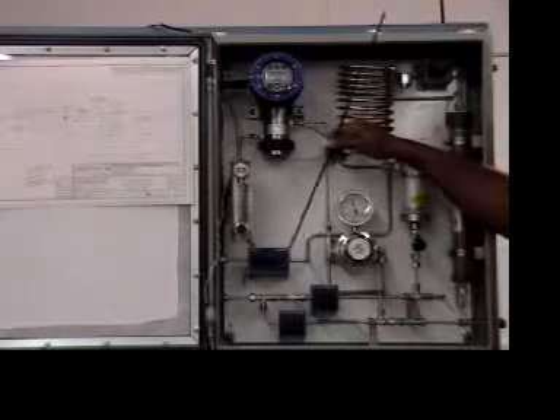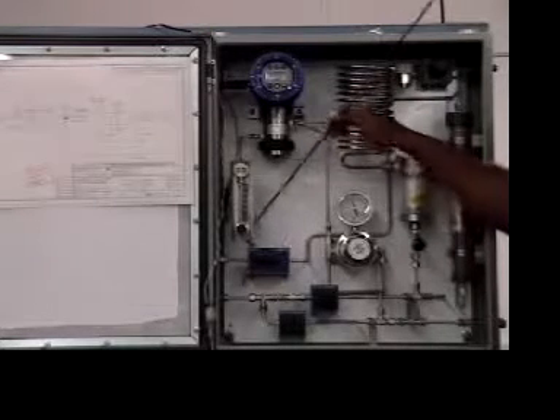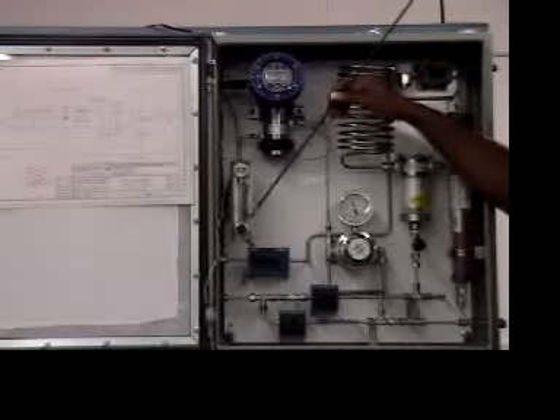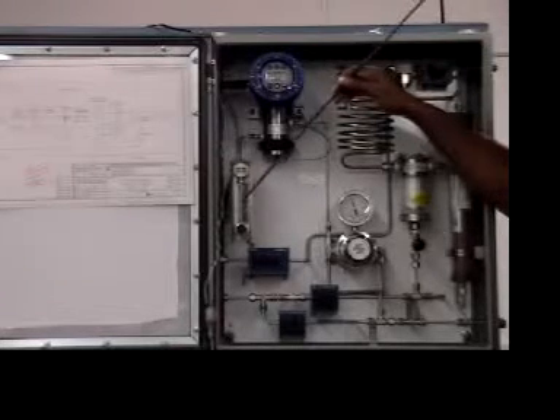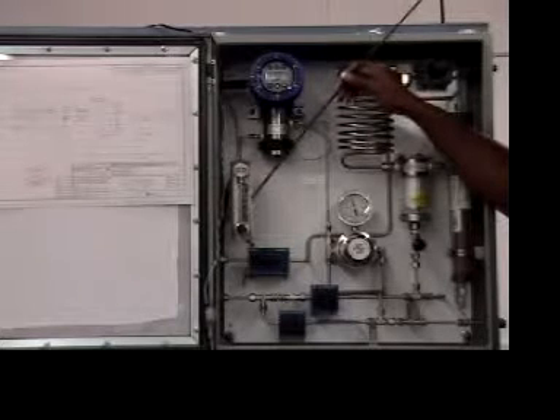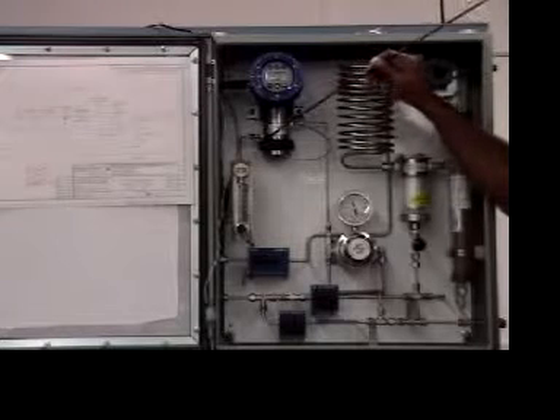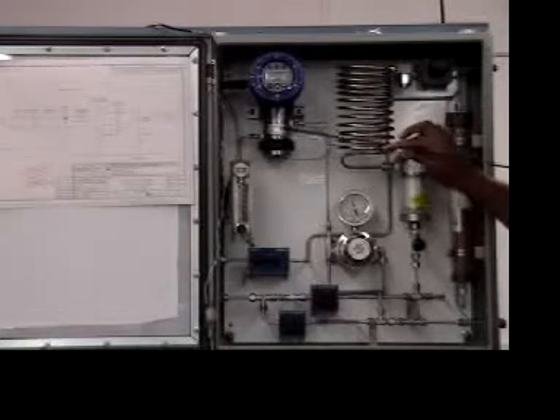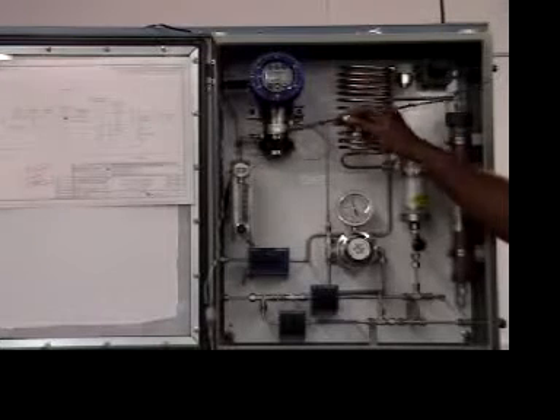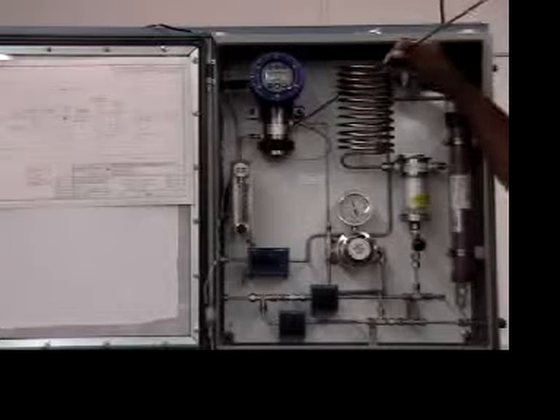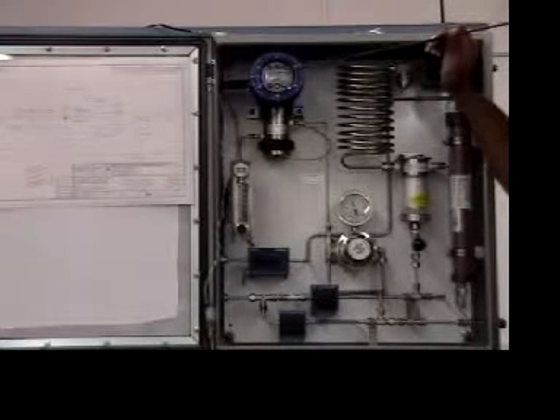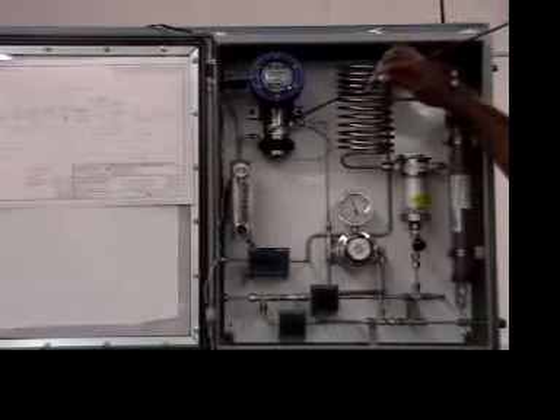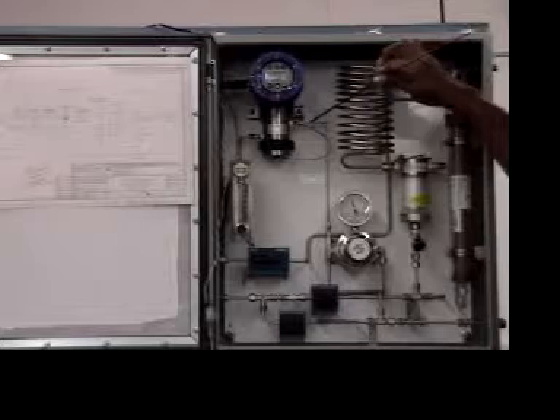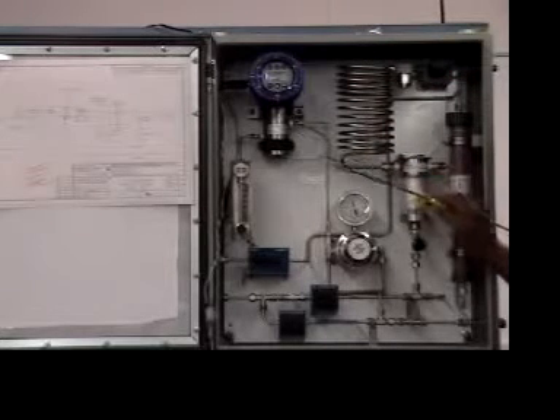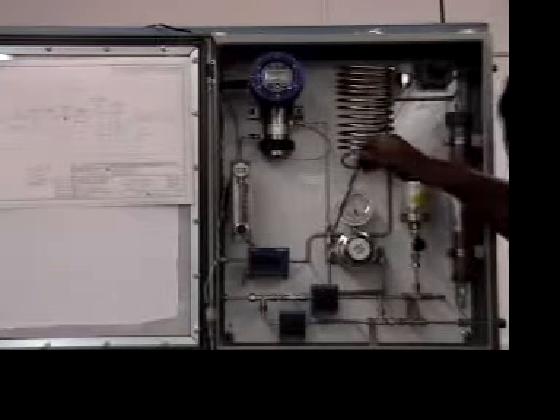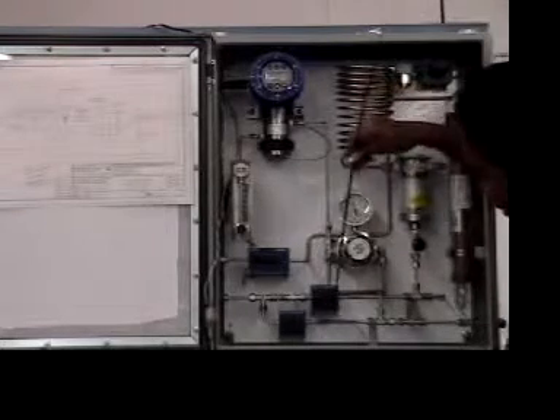So in the sample position, the gas from your sample goes through the flow meter. The flow meter should be set at a flow rate of about 100 to 150 cc's, and the sample continues through the flow meter and then into the analyzer. Once the gas sample passes over the sensor, whatever oxygen is being detected at the time is displayed on the display of the analyzer. The sample continues to the other side of the system and goes into this T here, which connects to the drain.